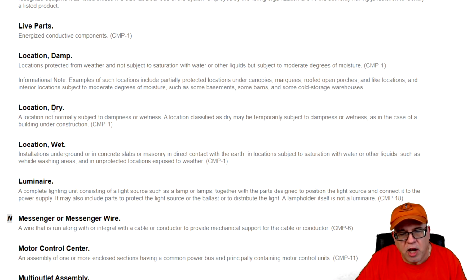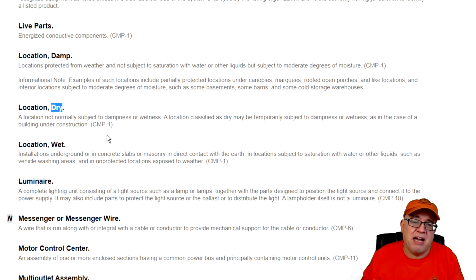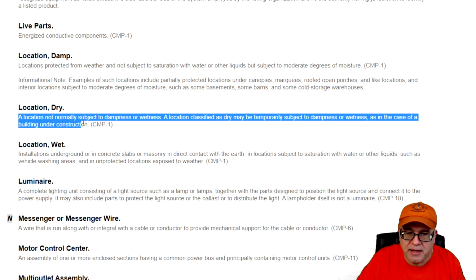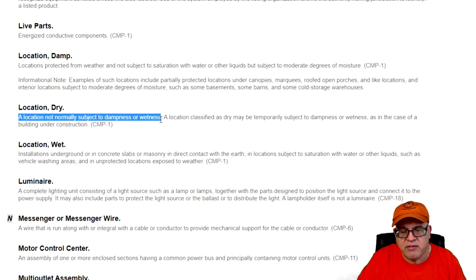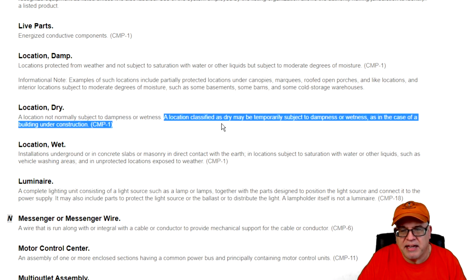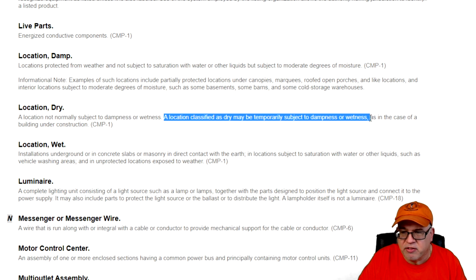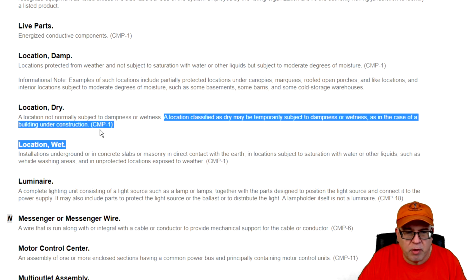Now, a dry location. What's a dry location? Any wall construction where the wire is going to be in the actual wall framing members and things like that, then that's a dry location. Okay? So let's look at it. It says a location not normally subject to dampness or wetness. It says a location classified as dry may be temporarily subject to dampness and wetness, such as in the case of a building under construction.